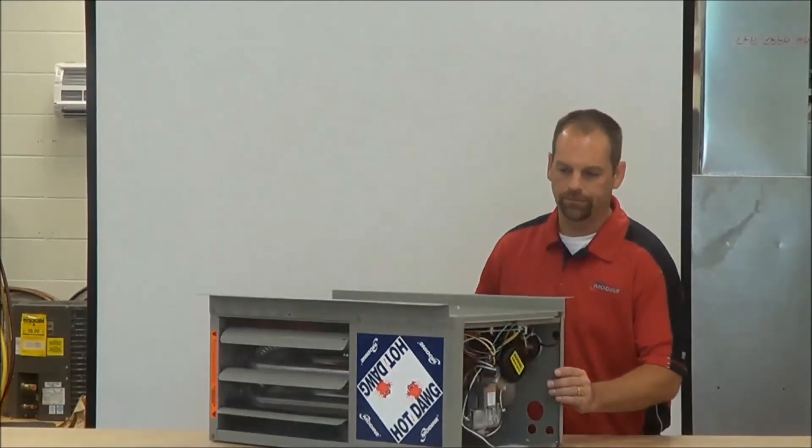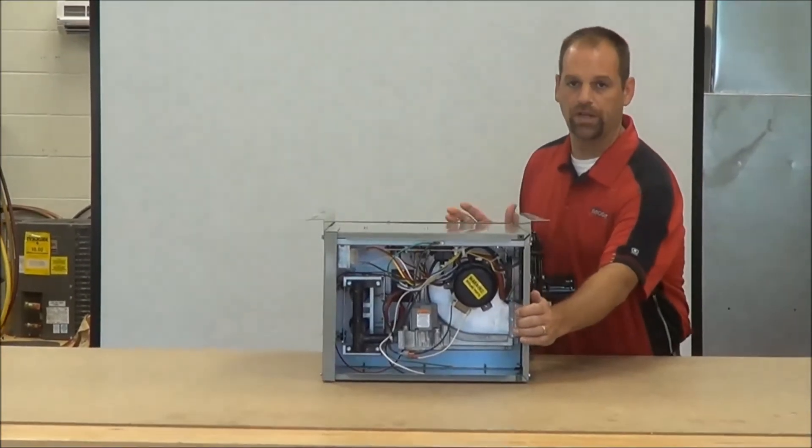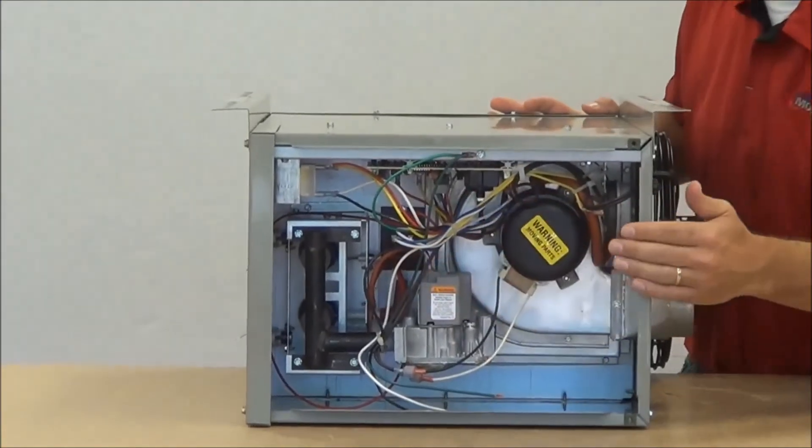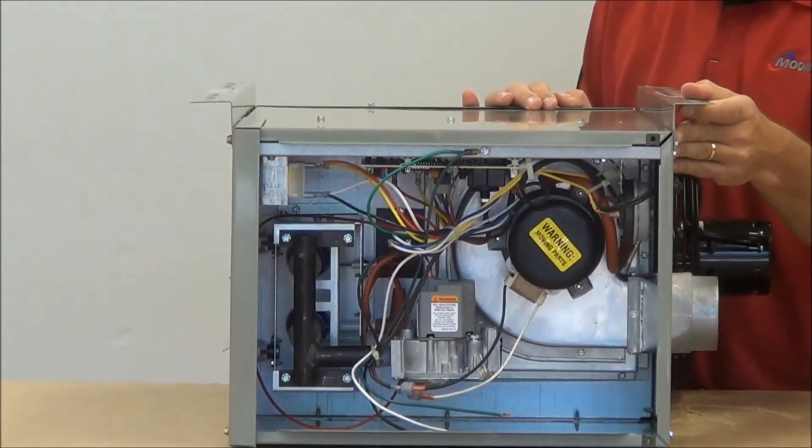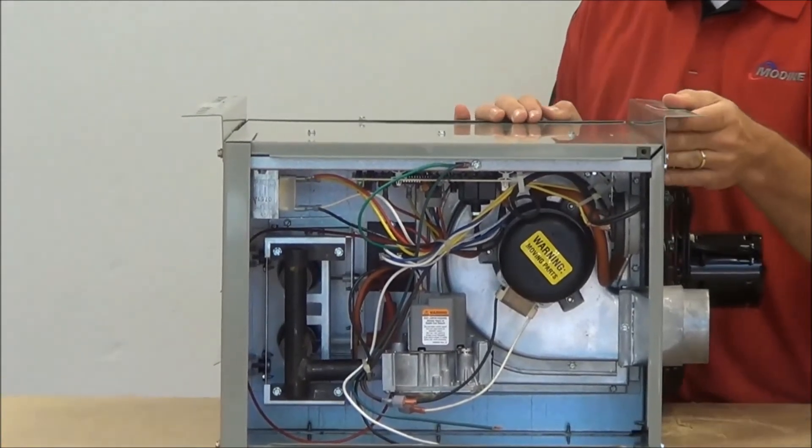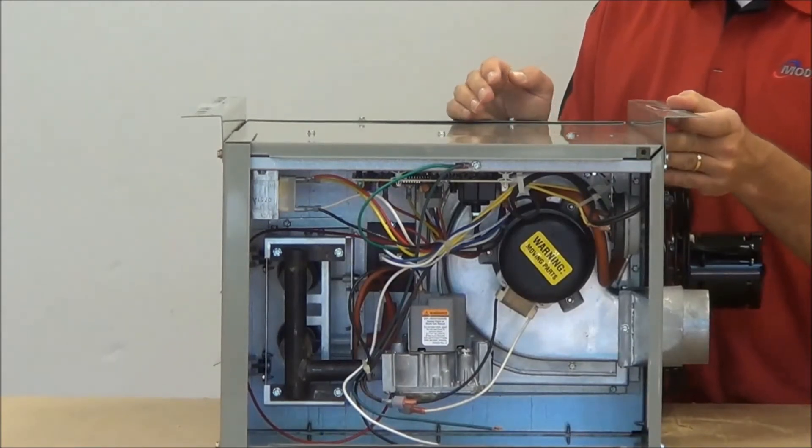This Hot Dawg unit uses in-shot burners which are pretty common now in the industry, located over on this side here. On this little guy here we only have two in-shot burners and what happens is the gas flows through each burner and it carries over and it lights the next one and so forth as it travels through the burners.